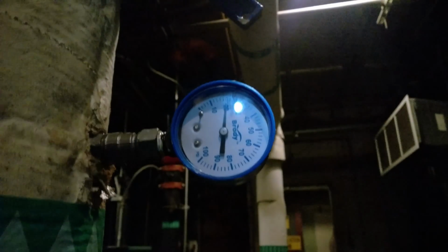Chiller room. It has pretty much moonlight in here because they put some LEDs and they do save electricity, but they're not very bright down here. Got all the pumps shut off. I shut these VFDs off because it seems like the closed loop for the chilled water is pretty much down at 0. So I got it manual filling right now. Got up to about 18. Yeah, about 18, 19, 20 psi. It's slowly filling. Get the bleeder up there.